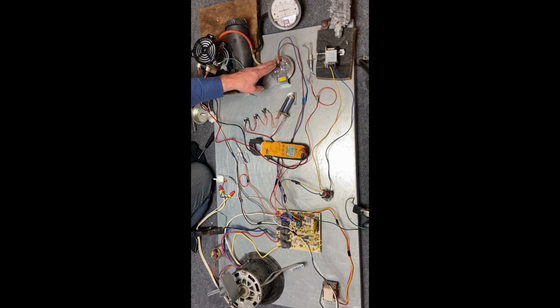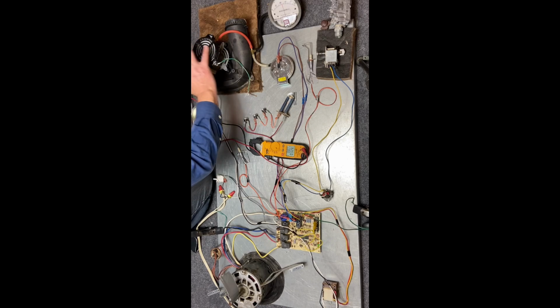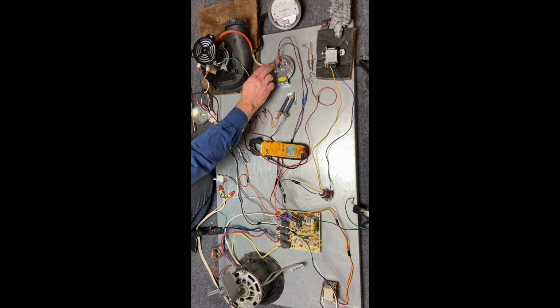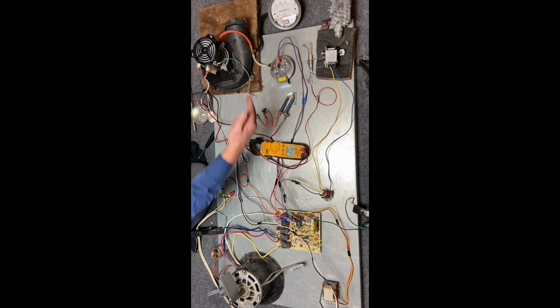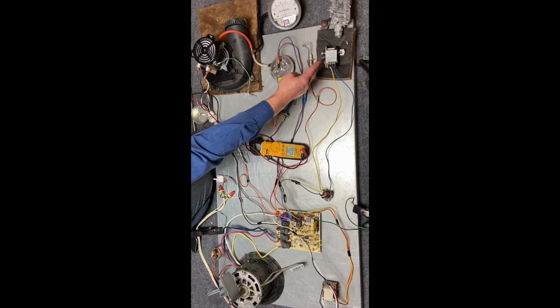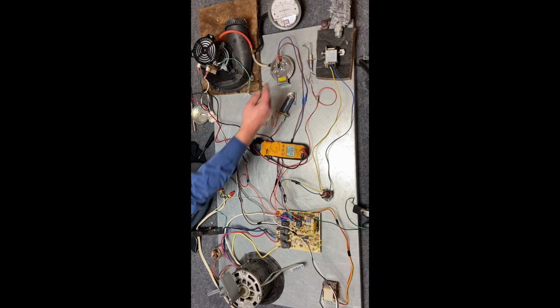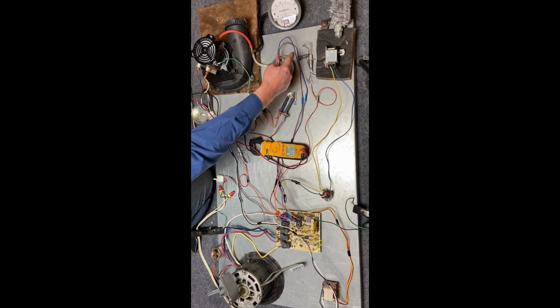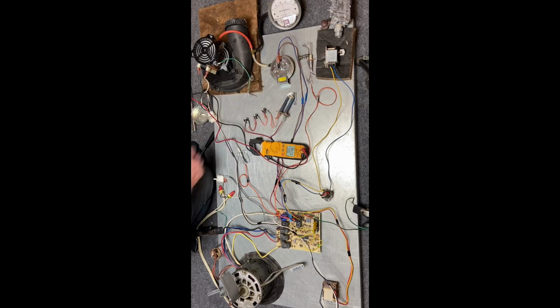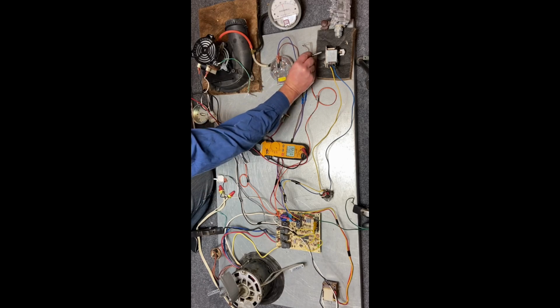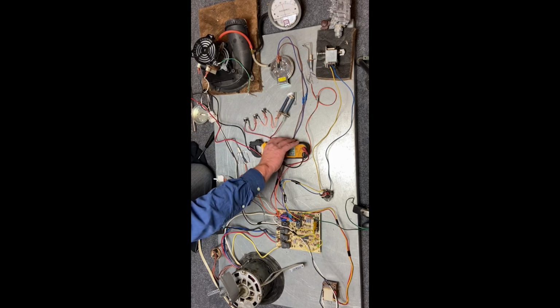If the switch is not closing and you don't have enough pressure, maybe it's the hose, maybe it's this fan motor in here, maybe something's happening, maybe this motor's not working, but you have to make sure it's 2 parts. I'm pulling a vacuum for that switch to close. That switch closes, the IFC knows, open the gas valve, energize the spark igniter, no flame, so it shuts off the spark igniter and closes the combination gas valve. It's a pretty simple little sequence. It's a pretty nice sequence.